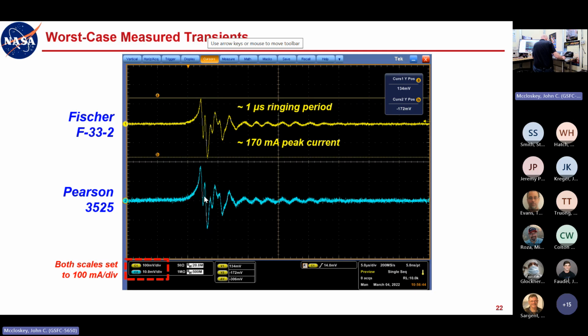The waveforms look pretty, not identical, but pretty darn similar, so I can basically believe either one of them. The Fischer one's a little more sensitive, so I probably just continued to use this one. It's not completely a damped sinusoid, but it's pretty darn close. It's something at least a damped sinusoid could represent. It's got about a 1 microsecond ringing period and about 170 milliamps peak current. So this was what we were measuring from the turnoff transients from those inductive loads, those thruster valves.